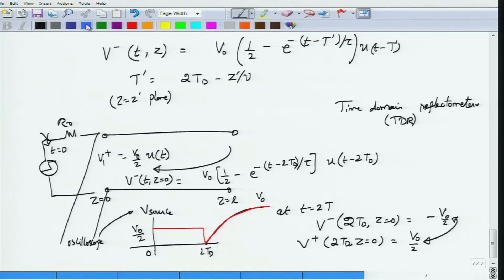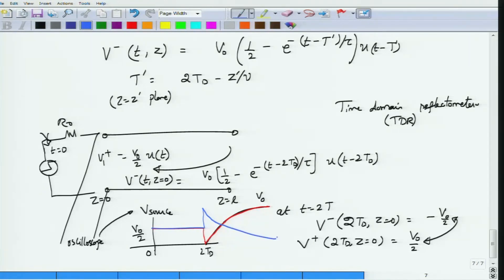To complete the picture: an inductive fault would produce a waveform that jumps up to V0 and then exponentially drops toward 0, whereas a capacitive fault drops to 0 and then rises toward V0. These TDR techniques are widely used to locate faults, much like radar.